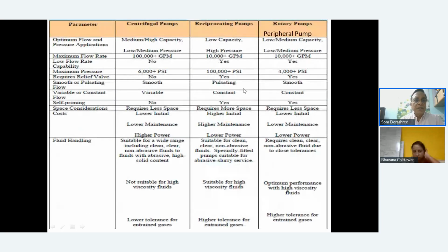Now, where are the applications for these? You have a comparative chart here: centrifugal pump, reciprocating pump, and rotary pumps, which are also like peripheral pumps. The optimum flow and pressure application: medium to high capacities for centrifugal, low capacity for reciprocating, and low to medium capacities for rotary. Maximum typical flow, this is in gallons per minute, so 1 lakh gallons per minute, 10,000 gallons per minute. And you have maximum pressure. Of course, the highest pressure is developed by the reciprocating pump, as you all know.